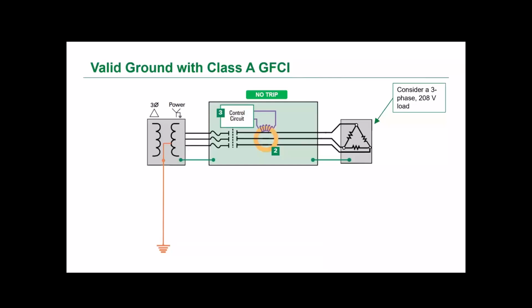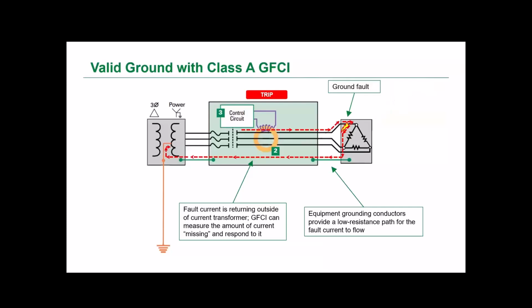So I want to show a simplified circuit and then get into a few cases here. This is a normal three-phase load connected to a Class A GFCI. As you can see, the green conductors shown on the drawing are the equipment ground conductors between the load and the GFCI, and from the GFCI upstream to the grounded power source. Now, if we add a ground fault from one phase to the equipment frame, the fault current will flow through the grounding conductor back to the source. So this path is the intended path with a low resistance, which will help minimize the voltage that could be present on the frame. And the current sensor can immediately detect this fault current, and the GFCI will trip within the time specified by the UL 943 standard.